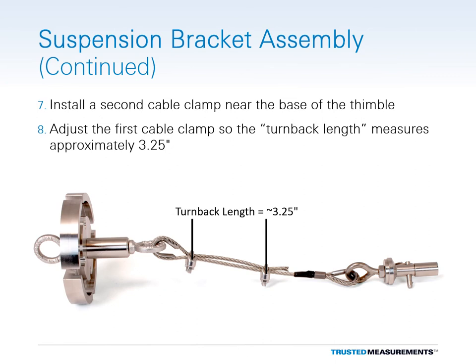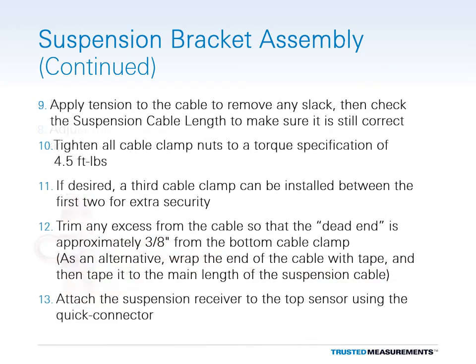Install a second cable clamp near the base of the thimble. Then adjust the first cable clamp so that the turn-back length measures approximately 3.25 inches. Apply tension to the cable to remove any slack, then double-check the suspension cable length to make sure it is still correct and adjust if needed. Tighten all four cable clamp nuts to a torque specification of 4.5 foot-pounds. If desired, a third cable clamp can be installed between the first two for extra security. Trim any excess from the cable so that the dead end is approximately 3/8 inch from the bottom cable clamp.